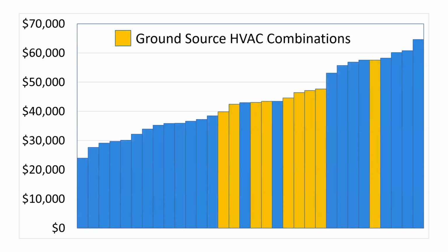The ground source heat pump system savings may seem surprising—we always think of geothermal as the best system, so you'd expect the highest cost savings, but these fall in the middle-ish of the group, mainly because the cost of natural gas is relatively cheap right now, and this option switches from gas to electric heating. If natural gas prices rise and electricity prices fall, this grouping would change significantly. And if we were looking at EUI instead of cost savings, these groups would be among the highest on the chart.